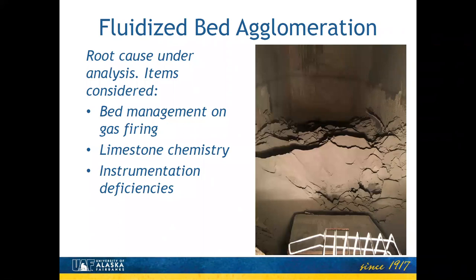Once you're in operation, it'd be the sort of thing that you don't turn it off any more often than you have to. Exactly. It might literally run an entire year or whatever before you have a planned maintenance event in the middle of the summer. Yep. So that's what we're looking into, to see what kind of instrumentation the boiler operator needs to get an indication that this could be occurring.